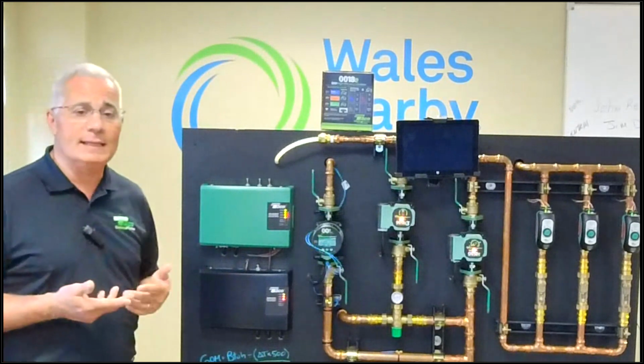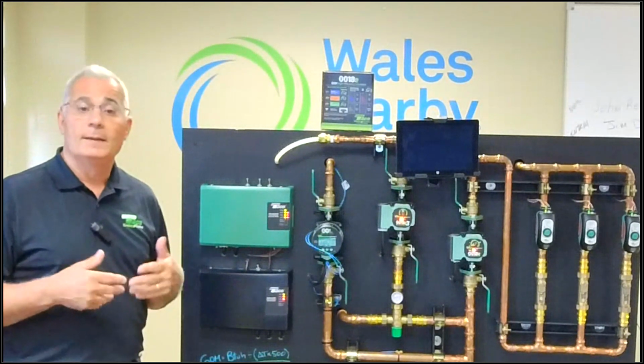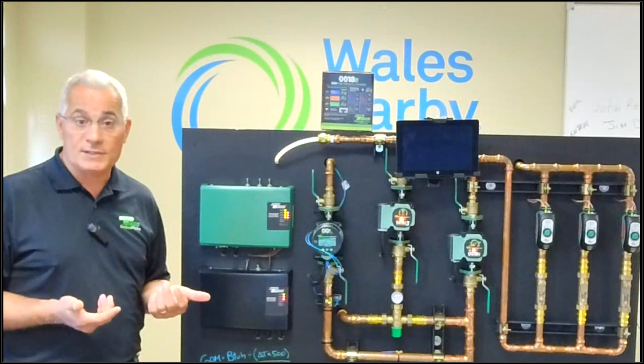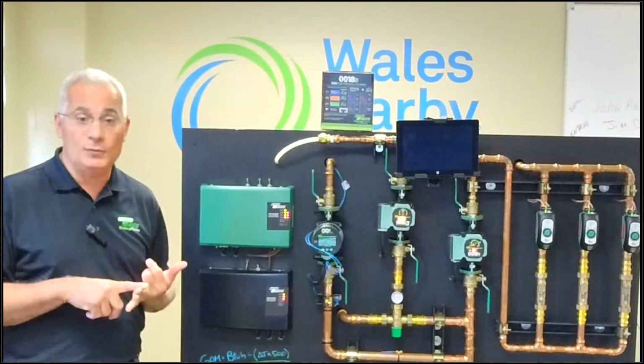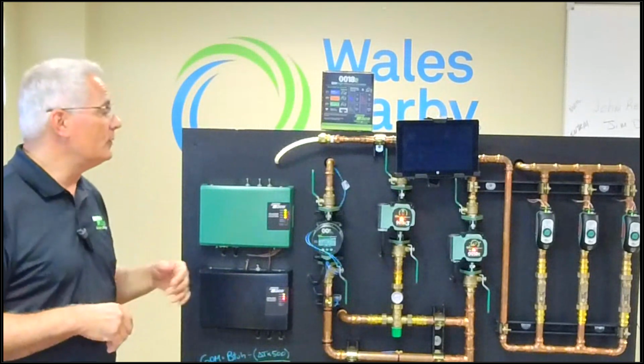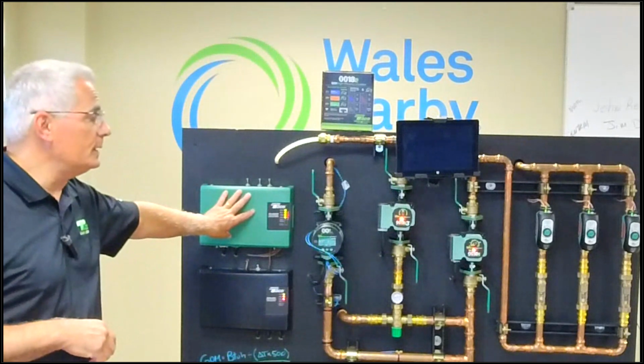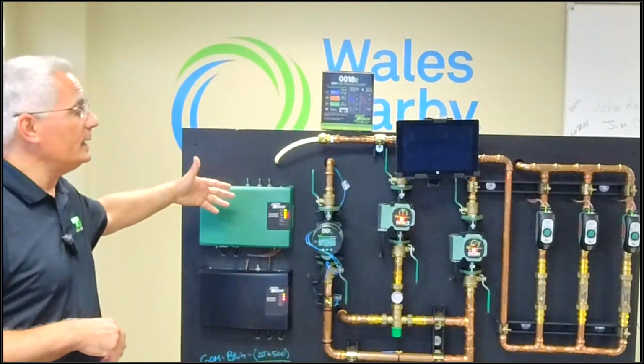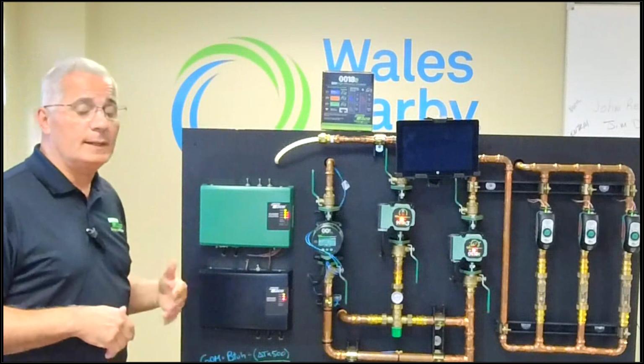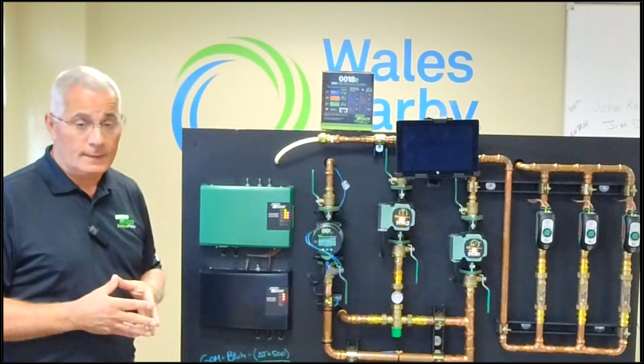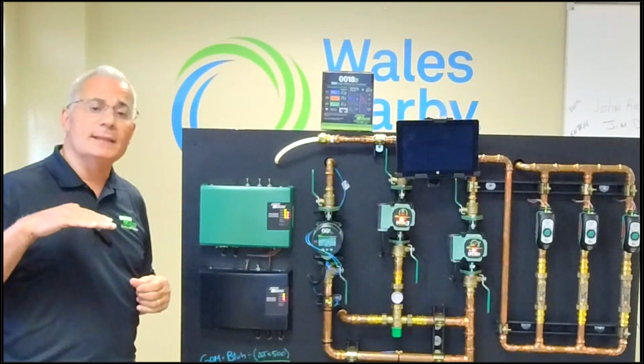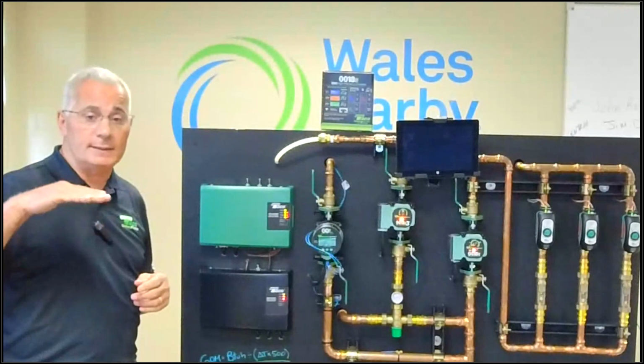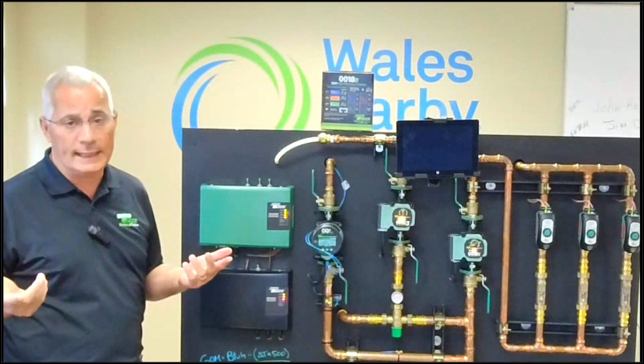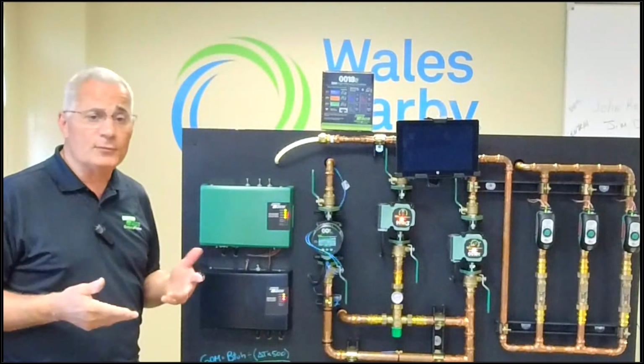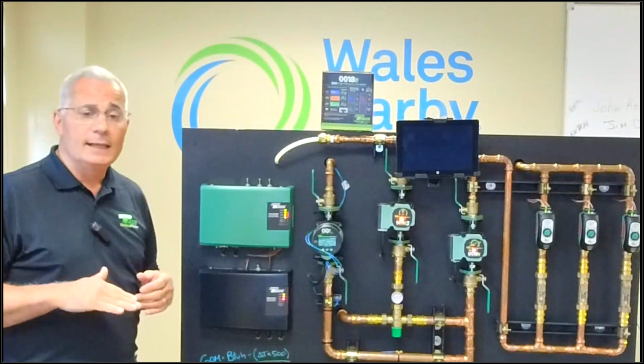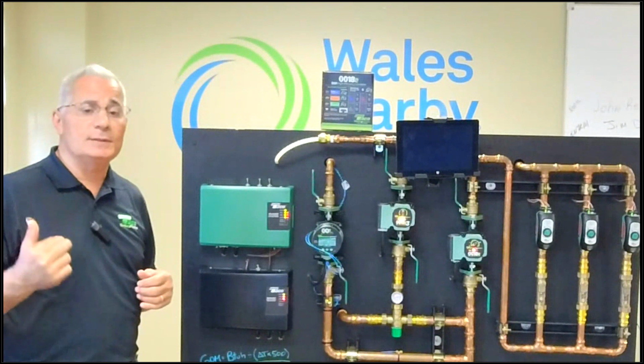So the more times I can keep the boiler off, more energy is saved, power is saved, and fuel. So if I plug in the PC700 here, I may get a call for heat. The boiler is going to fire. Depending on outdoor temperature, the boiler will fire up to a limit. Now, if it's really cold outside, it'll take it up to its high limit, 180.